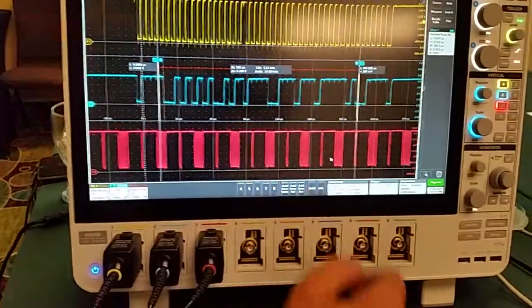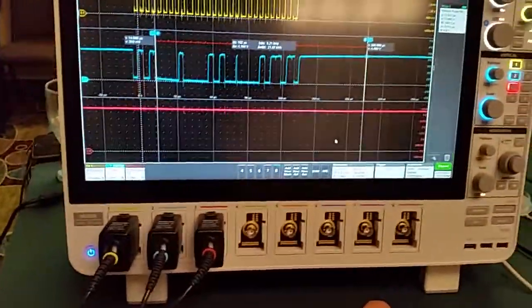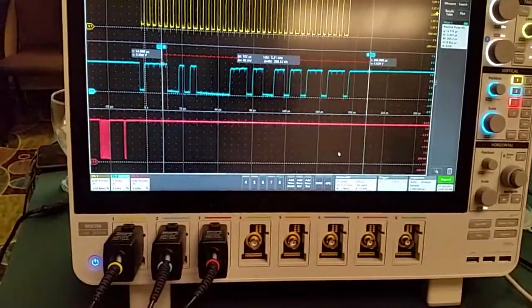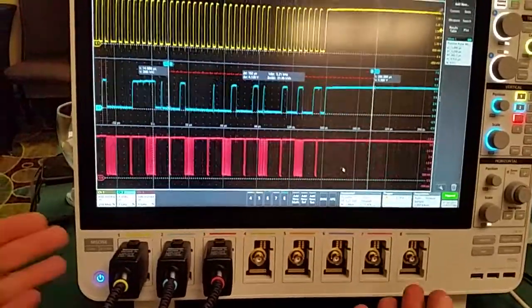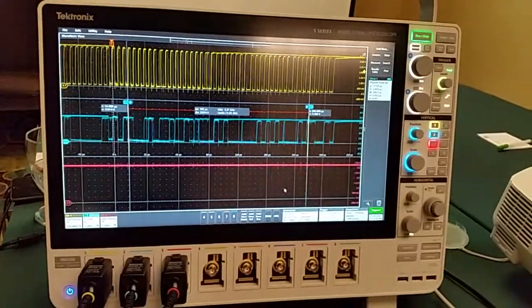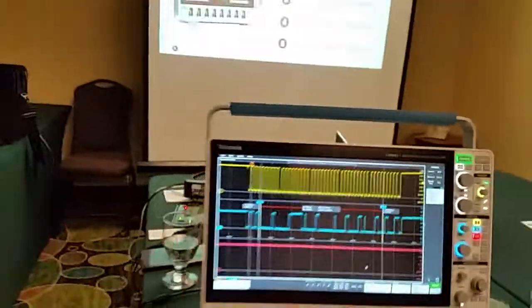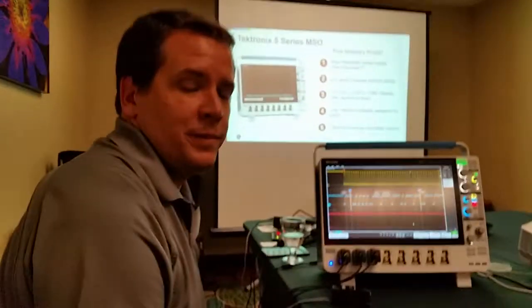Just go back to the channels quickly before we wrap up. So you can mix and match any number of channels on the flex channel? Yes. With this particular instrument here, anywhere from eight analog channels and no digital channels, all the way up to no analog channels and 64 digital channels.